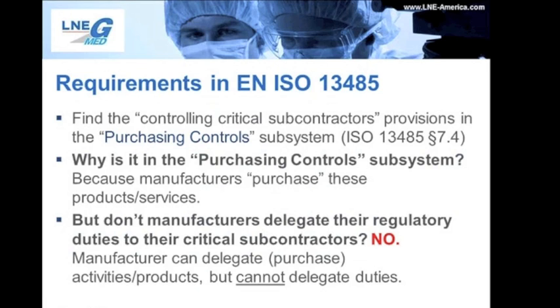So in this sense, even when the critical supplier supplies a service to the manufacturer, it is still purchasing something. Now, I should make an important distinction. A manufacturer can certainly subcontract tasks and services to a critical subcontractor. However, the manufacturer remains responsible for performing these tasks even if they are subcontracted. This means that even if a manufacturer subcontracts, say, manufacturing of a device from supply of parts through final assembly, the manufacturer retains the regulatory duties to supply parts and assemble a product that meets the essential requirements of the Medical Devices Directive. In this sense, a manufacturer can subcontract tasks, activities, or even products, but a manufacturer cannot subcontract or delegate away their regulatory duties, and that's true even if they don't physically perform them.